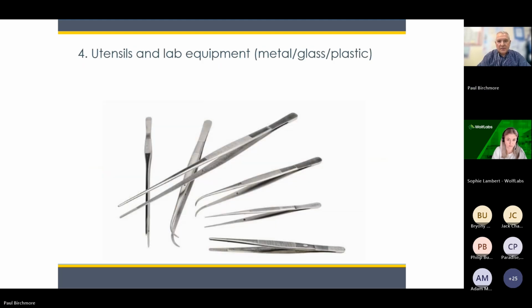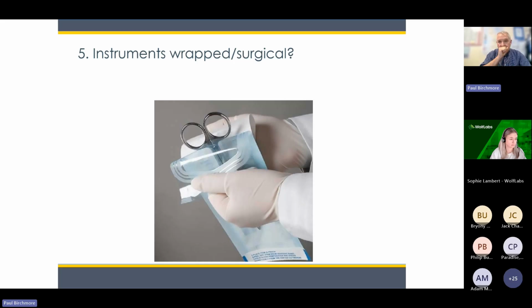Indeed, as Neil points out, you can use the standard unit, as it were, without those extra features for a discard load, but by using an autoclave with those extra features, a discard load could be processed more quickly. Another example of the type of loads is utensils. Examples like this are metal, plastic, glassware, perhaps, of particular shapes. Those we can treat as glassware. They're solid items in contrast to items that have been wrapped into a surgical pouch. This now moves towards acting as a porous load.